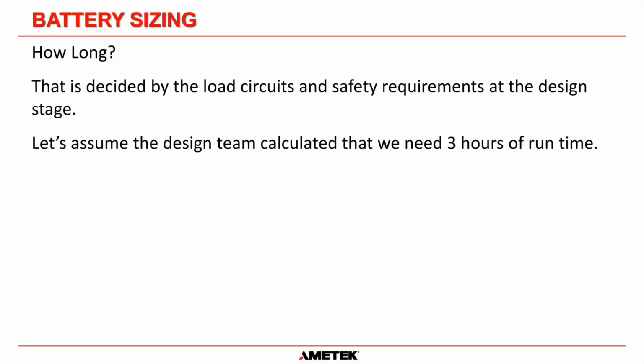The next question is, how long do we need that 86.6 amps? And that's down to the safety requirements that are put into the load at the design stage. For example, a huge data center only needs a backup time of about 15 minutes because they're trying to power the UPS while the emergency generators get up to speed, and then the automatic transfer switch transfers back to the generator.